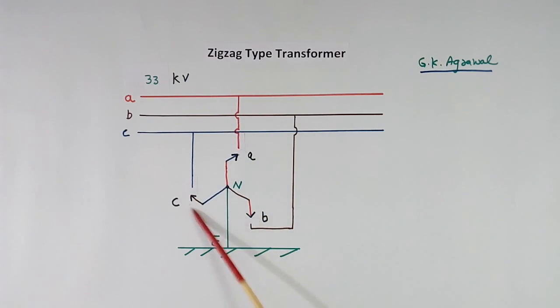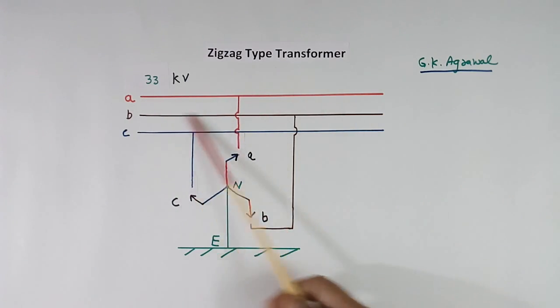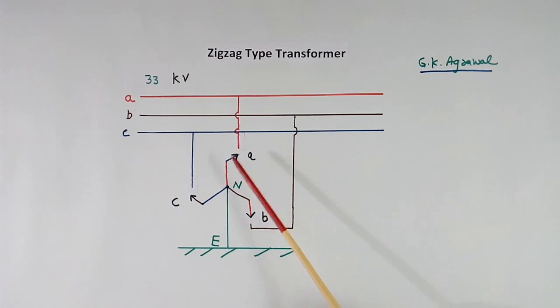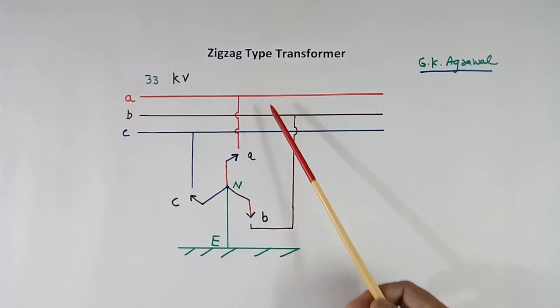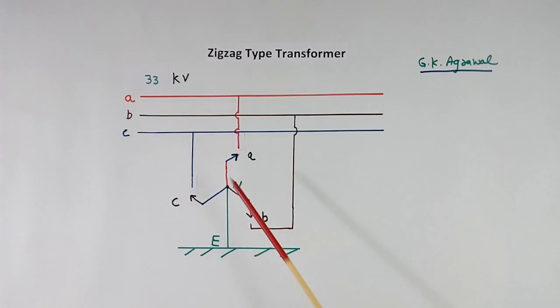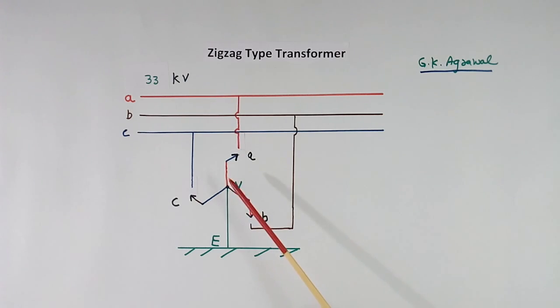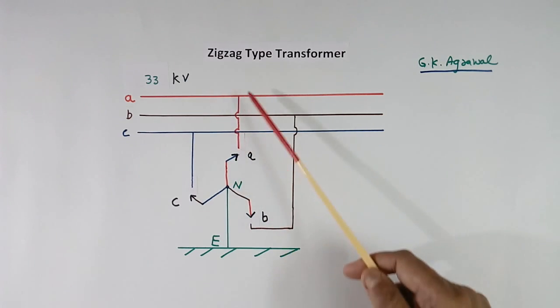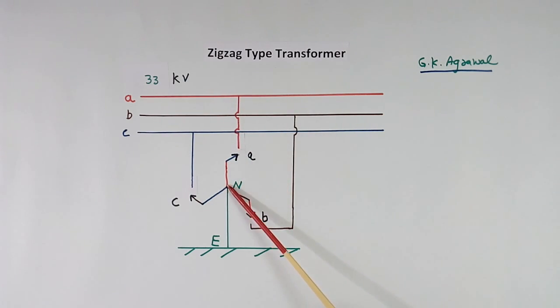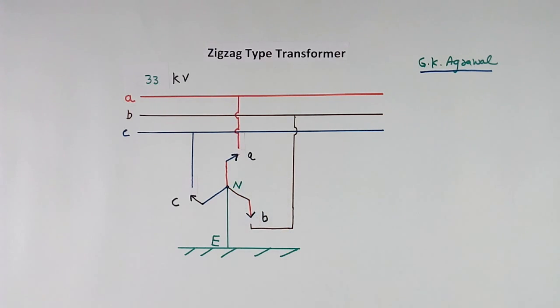There is a special type: the zigzag type transformer, which is used for third harmonic filtering and to generate an earth reference point. This is a zigzag type transformer connected to a 33 kV line — transformer terminals A, B, C are connected to the ABC high voltage line and the neutral is connected to ground. It has no load connected and no tapping, but simply connected to the line it provides grounding and filters third harmonics.